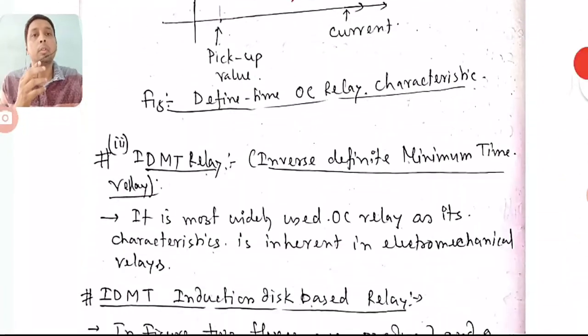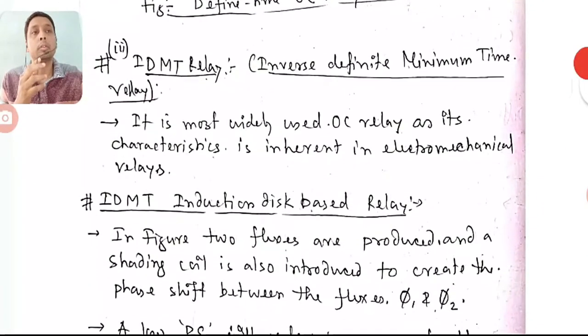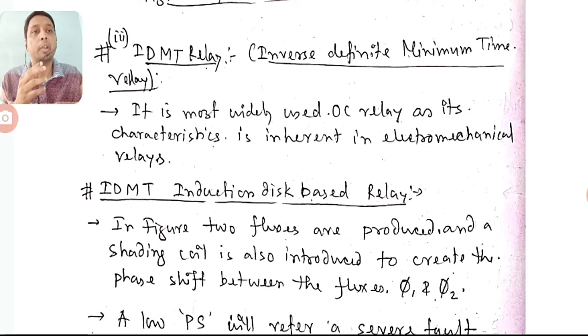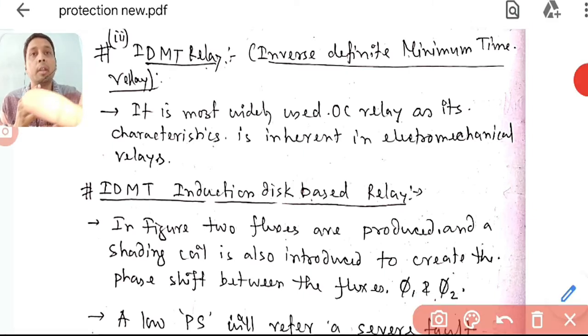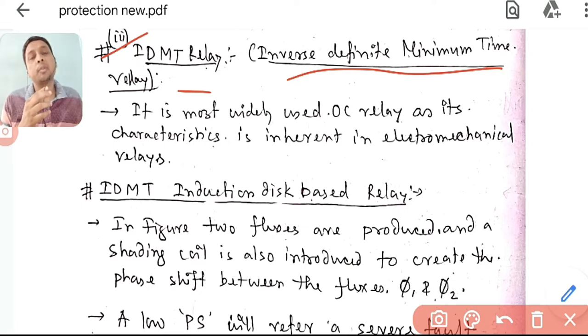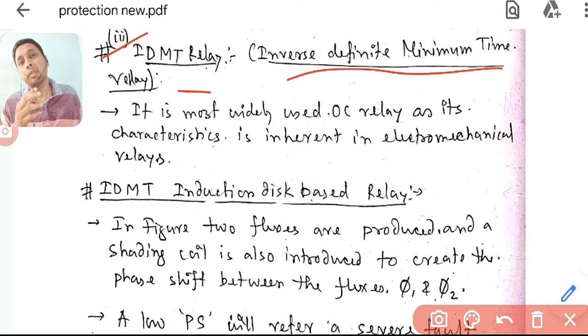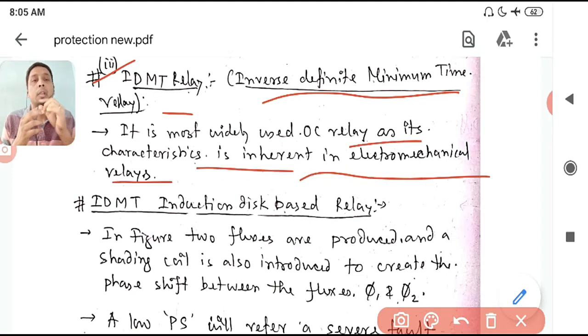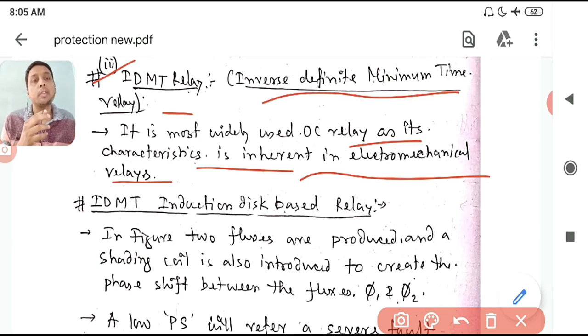We will start with IDMT relay. IDMT stands for Inverse Definite Minimum Time relay, and it is the most widely used overcurrent relay because its characteristics are inherent in the characteristics of electromechanical relays — both characteristics match, which is why it is widely used.